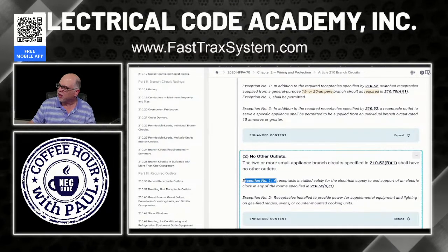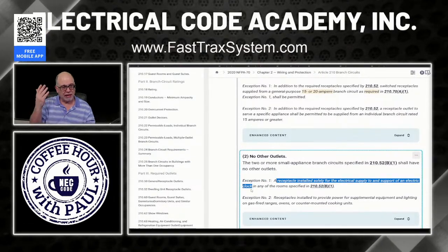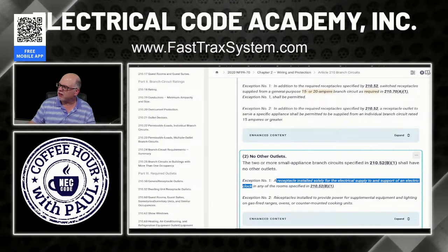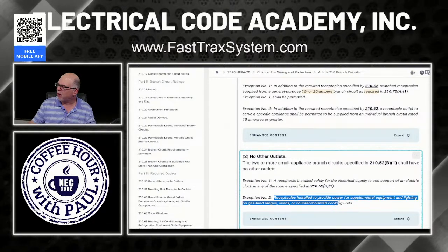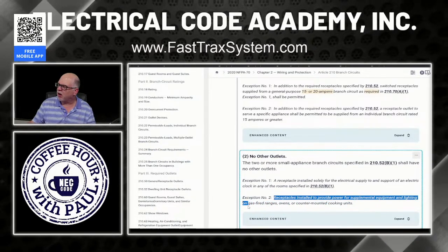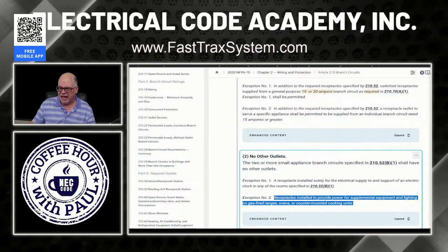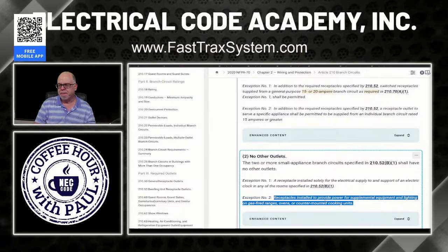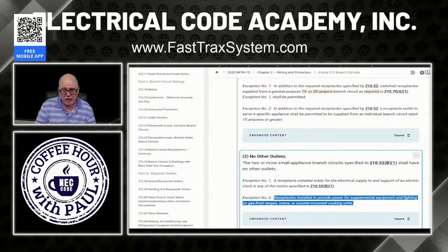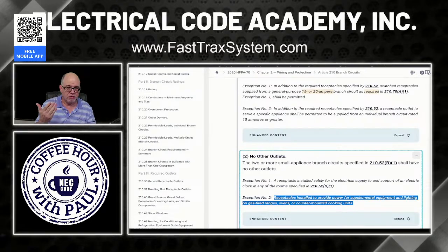Now, here are the exceptions. The first one right here that we just looked at, that's the one for the clock. That's okay to be on the small appliance branch circuit. The next one is exception number two. It says receptacles installed to provide power to supplemental equipment and lighting on gas-fired ranges, ovens, and counter-mounted cooking units. That's okay. So what does that mean? Well, maybe I have a gas range, maybe I have a gas cooktop, and all I'm trying to do is supply a receptacle for the igniter, right?